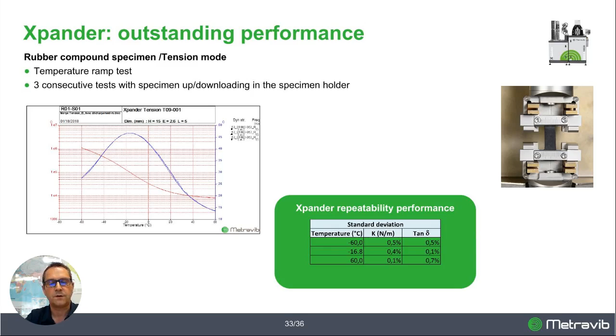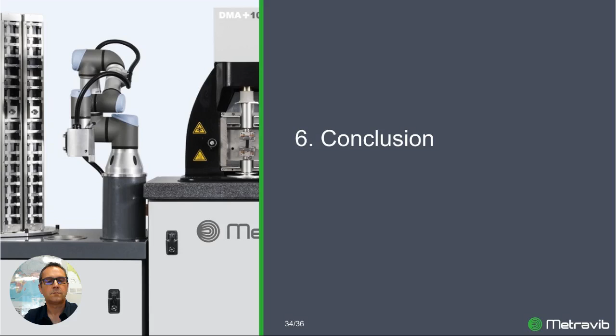And here another test, in tension mode in this case, with 3 consecutive tests as well on a temperature ramp test, to give an idea. Here we have a much softer specimen than in shear, of course, and you can see that the standard deviation we get on the stiffness is inferior to 1%, and as well for tangent delta.